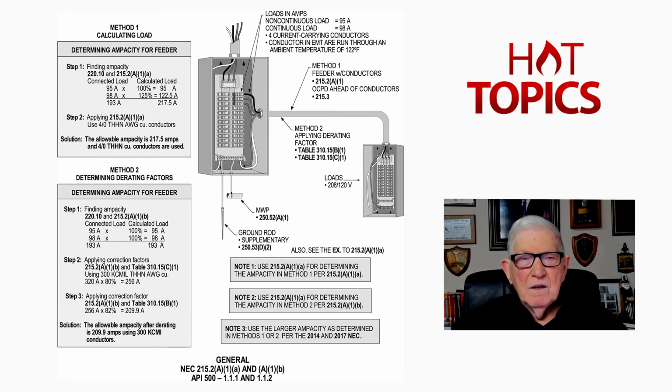Now we're applying 215.2A1 little b. Do you notice that the continuous and the non-continuous load is taken at 100%? And we come up with 193 amps.